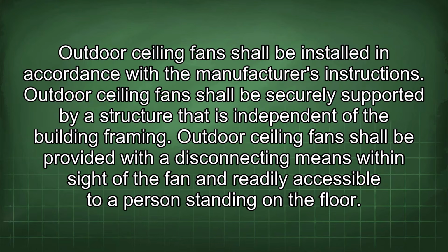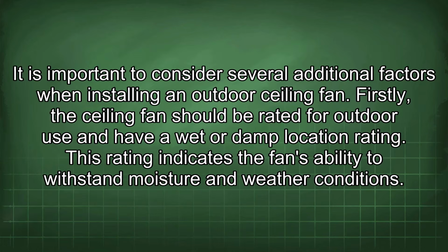Outdoor ceiling fans shall be securely supported by a structure that is independent of the building framing. Outdoor ceiling fans shall be provided with a disconnecting means within sight of the fan and readily accessible to a person standing on the floor. It is important to consider several additional factors when installing an outdoor ceiling fan.